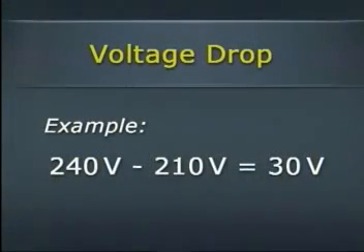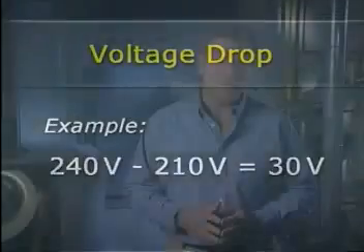Another factor to consider is the voltage drop in the conductors. The voltage drop is the difference between the measured voltage at the distribution panel and the measured voltage at the piece of equipment. Any drop in voltage is lost to the equipment. For example, if there are 240 volts at the supply and 210 volts at the equipment, there's a voltage drop of 30 volts. The maximum recommended voltage drop in any given branch circuit is 3%, which is 3 volts for every 100 volts being supplied.